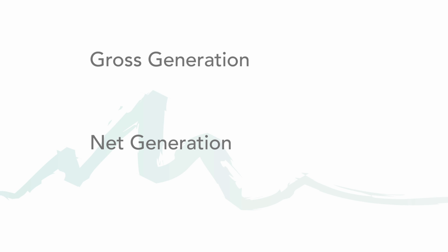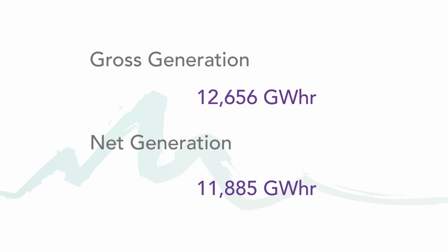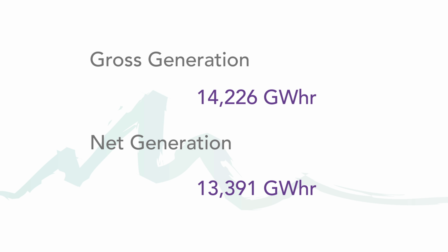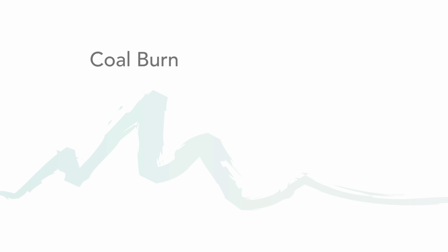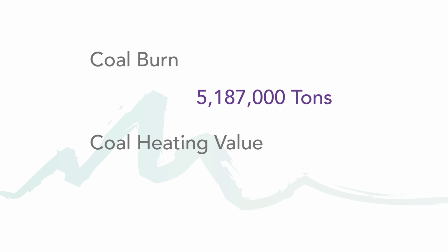The Intermountain Generating Station's gross and net generation was 12,656 gigawatt-hours and 11,885 gigawatt-hours, as compared to a 10-year average of 14,226 and 13,391 gigawatt-hours. Coal burn was 5,187,000 tons, with coal heating value of 11,190 BTU per pound.